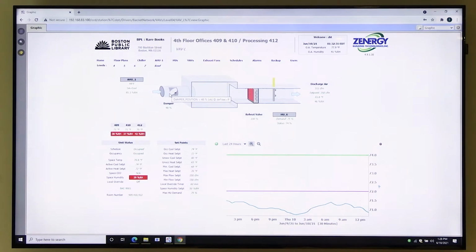As the damper starts to open, and say as it gets hot out, all the dampers in all the spaces start to open, your air handler fan needs to make up the difference, because now we're looking for all this more air, so your fan speed needs to ramp up. The way it does that is it's monitoring the pressure in the duct that's feeding into this box. As that pressure drops, as all those dampers start to open, the fan starts to ramp up and accounts for that. So the whole system works all together.